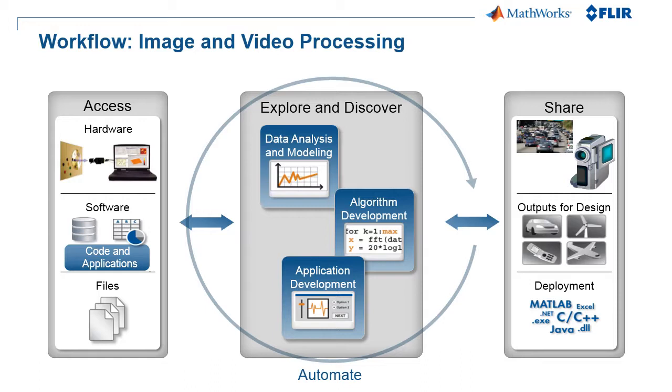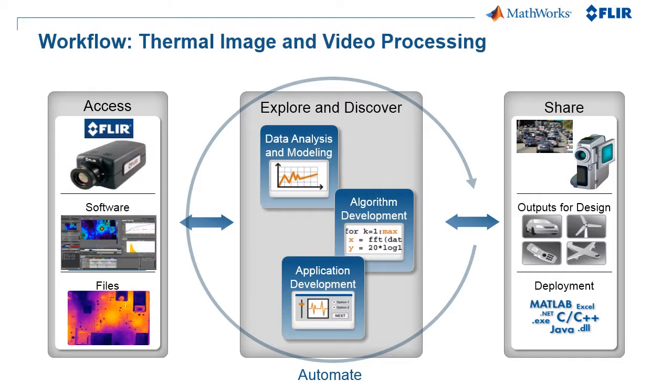Now, if we move to thermal imaging, really the only subtle changes, if you see in the access area, is that we're working with real hardware, real thermal cameras from FLIR, and we'll talk about how we connect to some of those in a minute. We're actually working with their software. So, what I mentioned earlier, we have a surprise. We have a way, we'll show you later, of how we connect more intimately with their Research IR software and exchange data back and forth. And then finally, if you had cameras, for example, that are saving files, these temperature files, we can import those in directly as well. So we're going to go through this workflow and use this exact workflow through the next couple demos.